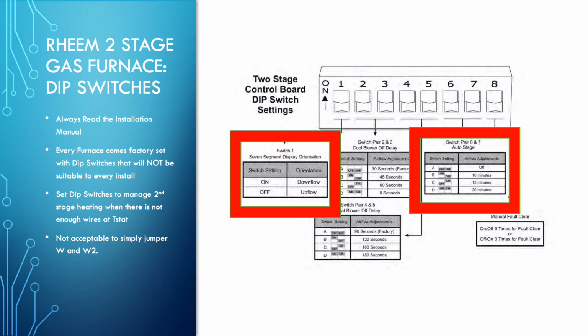For service technicians, while I'm on that note, pay attention. You're out on a diagnostic or you're doing a tune-up on a gas furnace and you have the panel door off. You test the system with a jumper, you fire up the furnace, you check everything, see how the flames are looking, see how everything's operating, checking amp draws, and then you're ready to do some cleaning and you just let go of the door switch and shut the system off right away. So the blower kicks off and the flames cut out, the inducer draft motor and the gas valve shut down. So what you didn't do in that scenario was allow the blower long enough to run for cooling off the heat exchanger, whether it's an 80% or high efficiency with a secondary heat exchanger. You need to let it run long enough to actually cool down the furnace before you remove power.